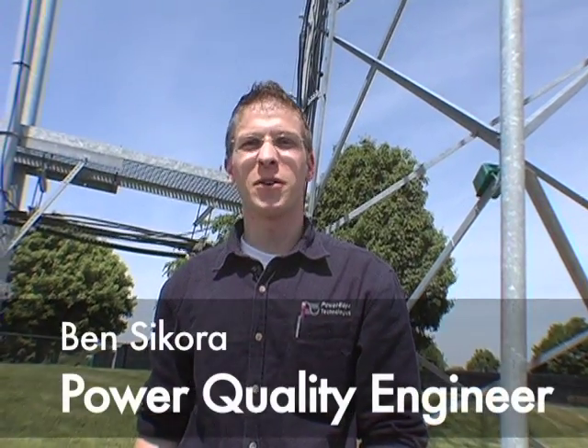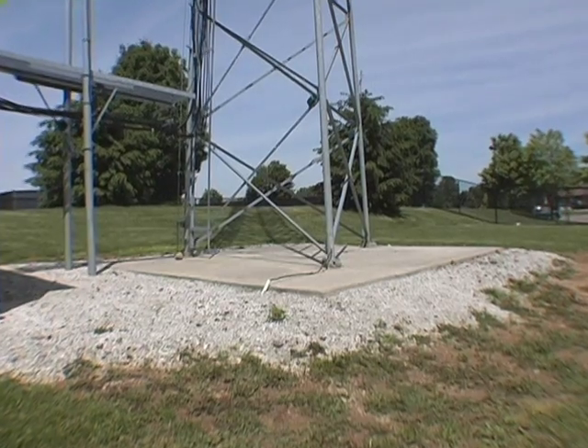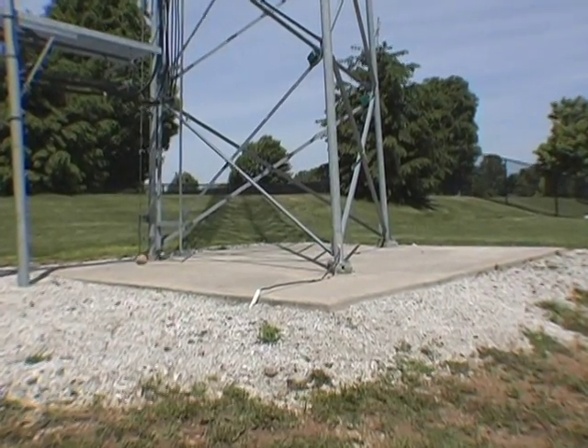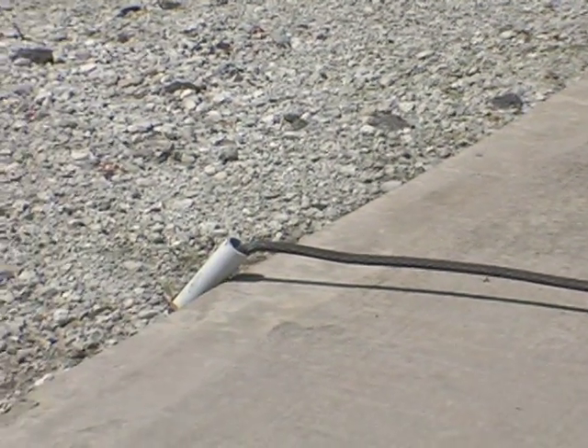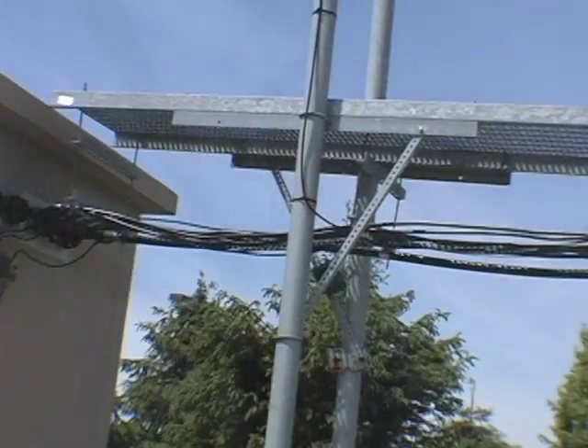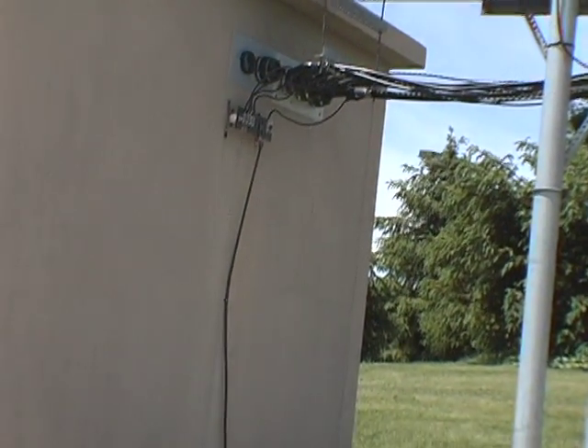Our goal was to create a single earth reference point for this communication system. To do that, we came off of each tower leg with a four rod, and each one went to a ground rod. Then from the ground rods, we installed a ground ring around the entire communication tower, and we bonded the electrical panel and the communication cable all to this same system.